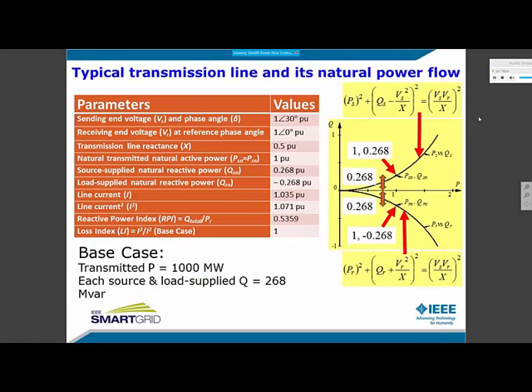Consider a typical scenario where the transmission line is operating with a 30 degree power angle and has 0.5 per unit reactance. If we assume this line is carrying 1 per unit load, which is 1,000 megawatt, maintaining the voltage at both ends of the line, this line also carries some reactive power. The reactive power comes from the load end and the source end. Since we have seen the power flow equations as sine and cosine functions, we can combine them to create this circle equation. So one characteristic represents the circle or PQ relationship at the load end of the line, and one represents the PQ relationship at the source end of the line. It shows that for 1,000 megawatt of real power flow, we need 268 megavar of reactive power from both ends of the line.